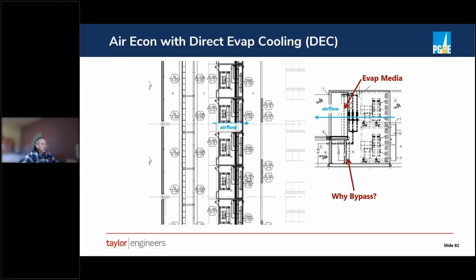So the two main reasons are temperature control. Evap media is not easy to control. It's sort of an on-off thing. And we'll get into that detail more, but let's just say that this is a single stage of evap media. If you turn it on and cooled all of your air, it would overcool and potentially over humidify. And so basically you blend air that's overcooled with air that's undercooled to get a combination that's at the right temperature and humidity for your supply. In this case, this design had what I would argue is somewhat of a fatal flaw.